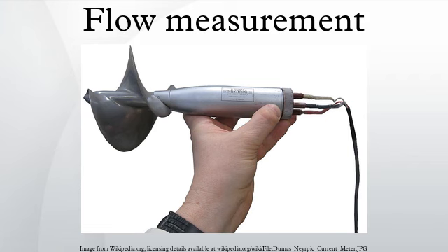The Woltman meter comprises a rotor with helical blades inserted axially in the flow, much like a ducted fan. It can be considered a type of turbine flow meter. They are commonly referred to as helix meters, and are popular at larger sizes.